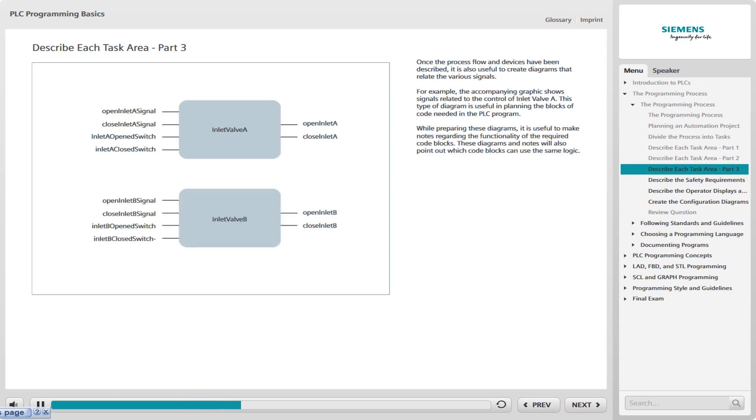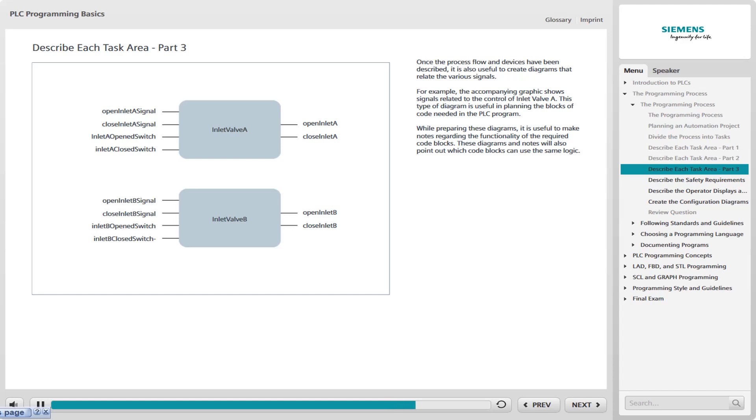While preparing these diagrams, it is useful to make notes regarding the functionality of the required code blocks. These diagrams and notes will also point out which code blocks can use the same logic. For example, although the inputs and outputs associated with inlet valves A and B are different, the functionality is the same. So a reusable block of code can be used with different inputs and outputs during each instance of the block use.